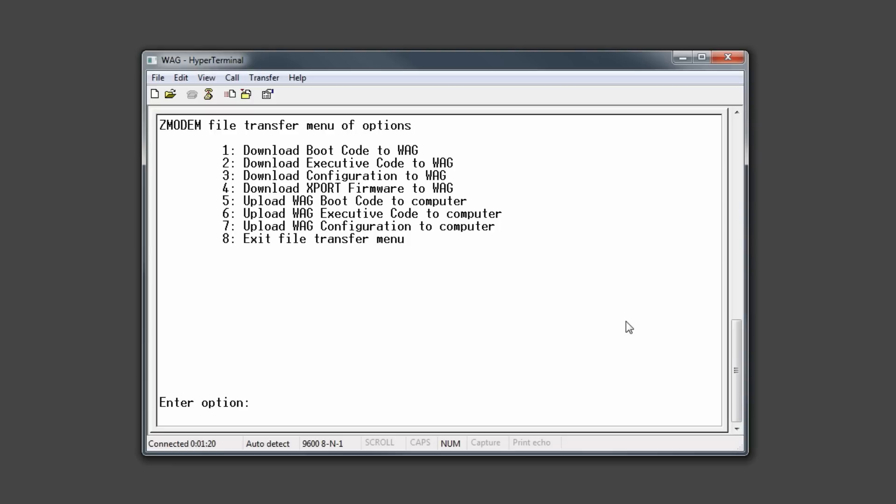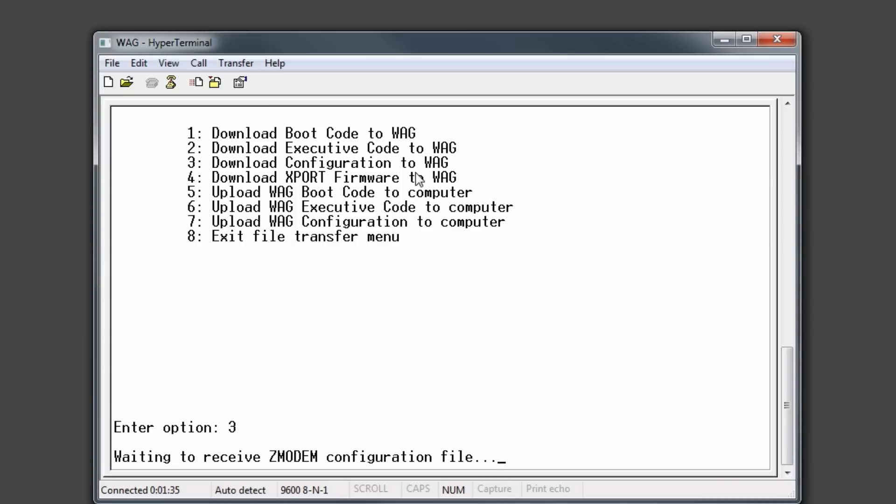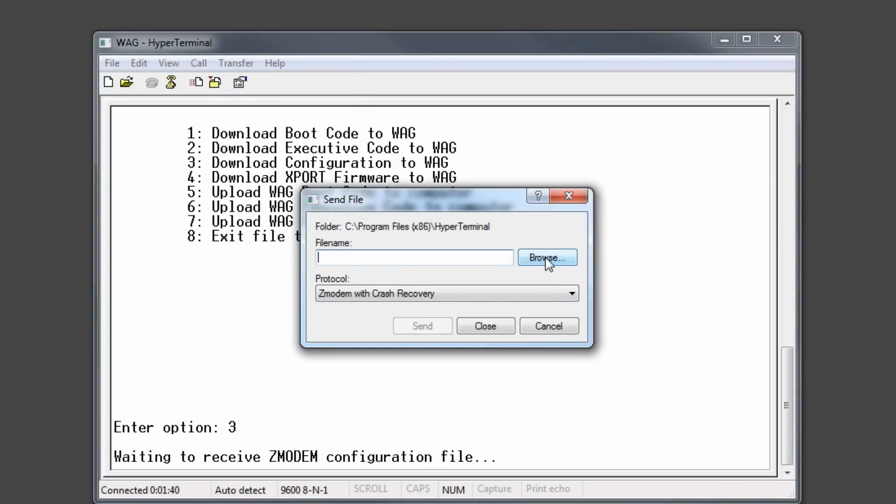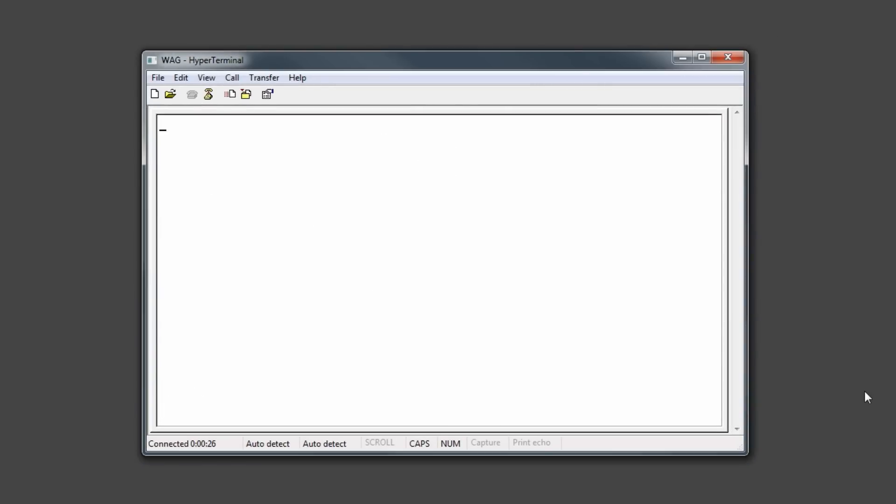Every site will require a configuration file to be downloaded. This is also accomplished using the X file command. In the X file menu, select option 3 to download a configuration file to the WAG and press enter. Next, using hyperterminal, click transfer, send file, and browse to the configuration file you wish to upload. Having a configuration file ready for each site ahead of time saves a lot of time in the field because you will not have to go into individual settings and modify them. After loading a configuration file, you will want to check all of your configuration settings and also make any changes necessary.